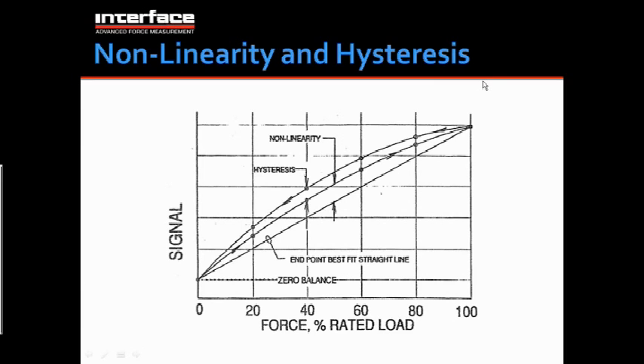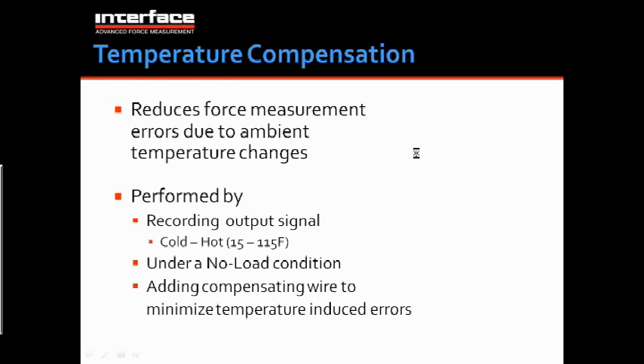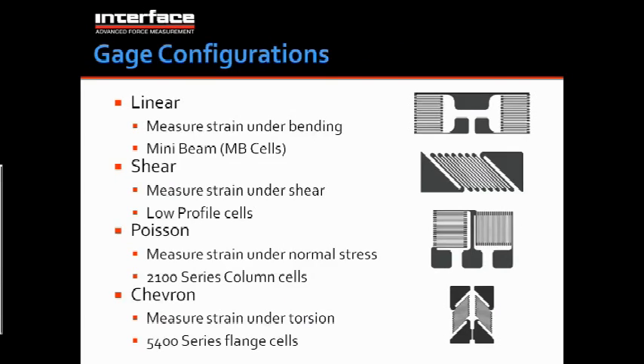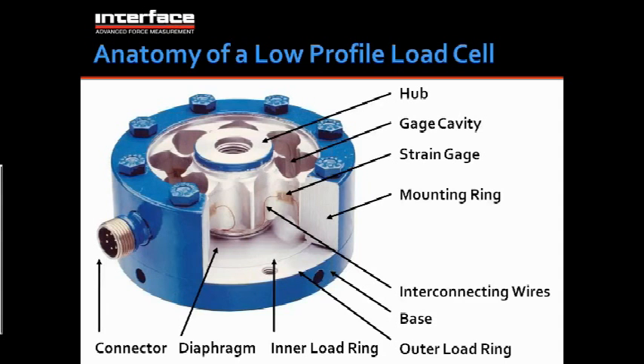Okay, the diagram earlier looked like it had more than 4 gauges. Why was that? I'll take it. I think they're probably referring to the load cell cutaway that we showed early on. You're correct. There are 4 beams here that would be gauged for this lower capacity unit, and there would be 8 gauges on there. You really only need 4 gauges for a complete bridge. We put 8 gauges on every low profile to lend much better eccentric insensitivity. So with 8 gauges, you can wire them up so that they tend to self-cancel for non-axial loads that are applied. And then we take it one step further with our moment compensation process.